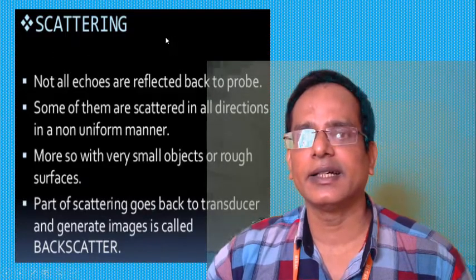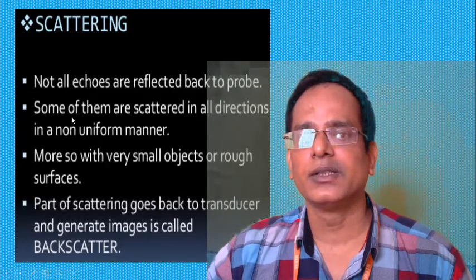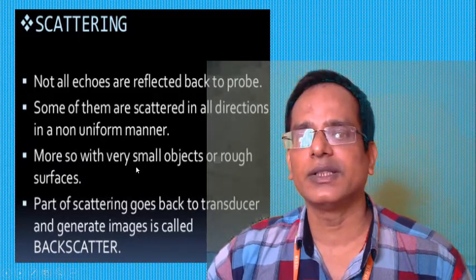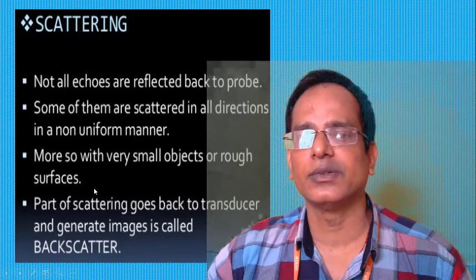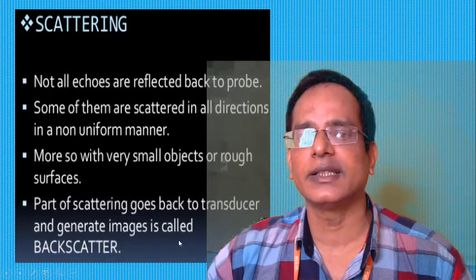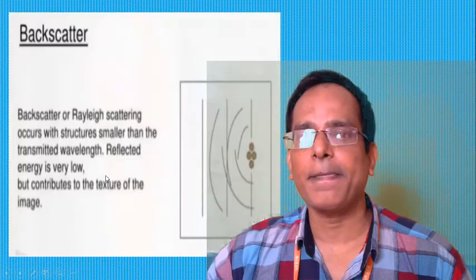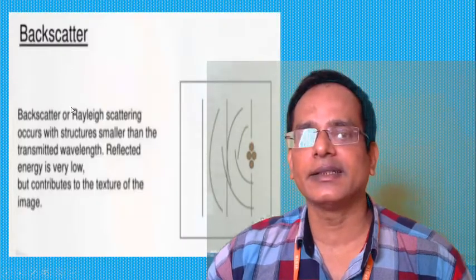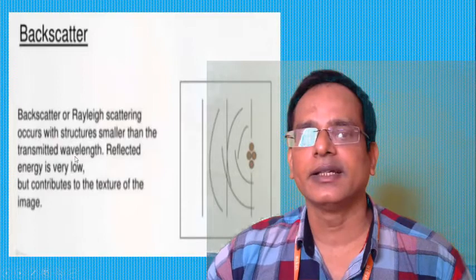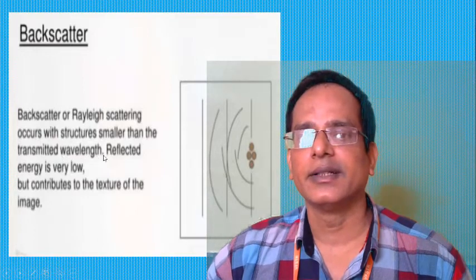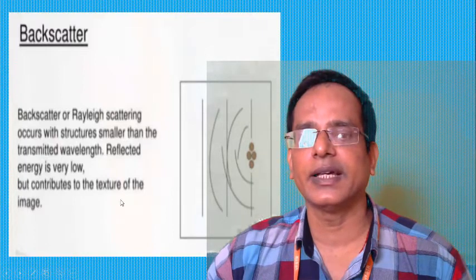The fourth tissue reaction is scattering. Not all echoes are reflected back to the probe; some are scattered in all directions in a non-uniform manner, particularly from very small objects or rough surfaces. The portion of scattering that returns to the transducer generates an image called backscatter. Backscatter, or Rayleigh scattering, occurs with structures smaller than the transmitted wavelength, and the reflected energy is very low but contributes to the texture of the image.